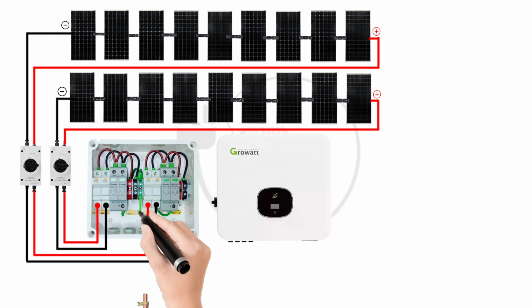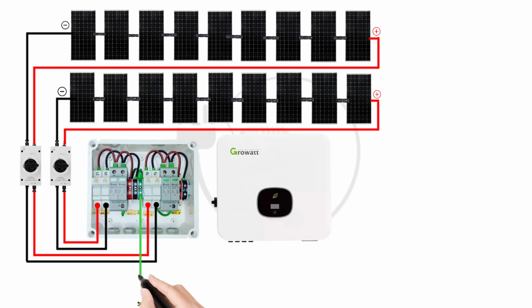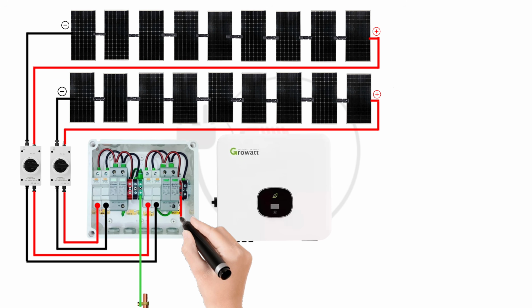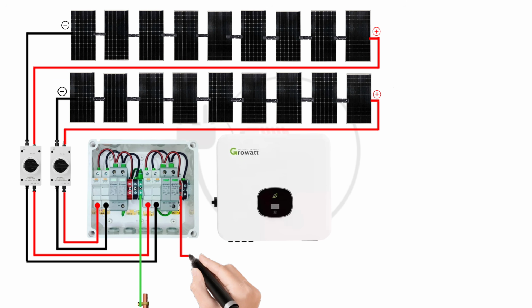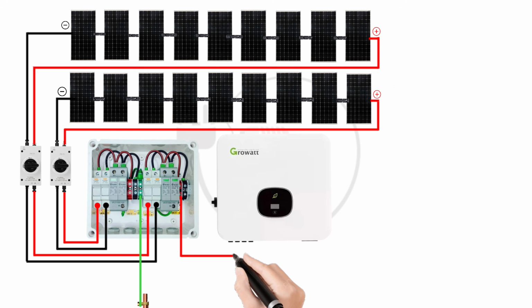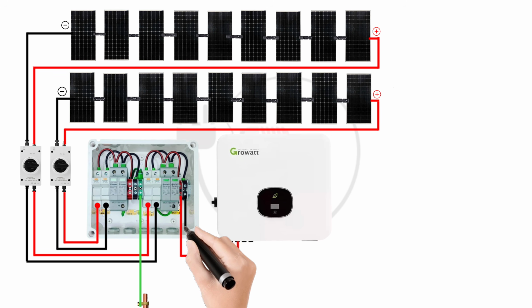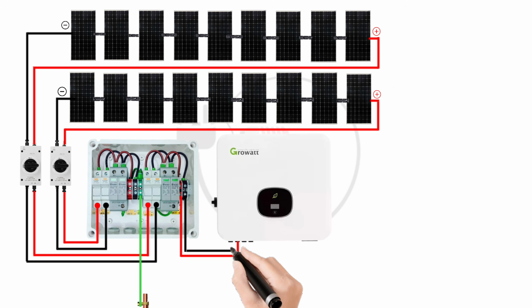Earth connection. Connect the earth terminal of the SPD to the ground in the earthing system. MCB output to inverter. Connect the positive output of the MCB to the positive PV input of the solar inverter. Connect the negative output of the MCB to the negative PV input of the solar inverter.